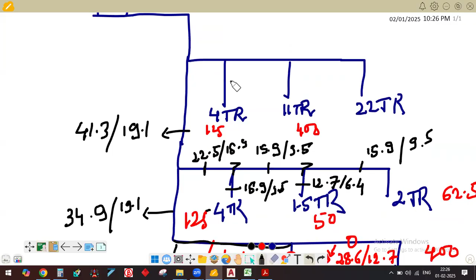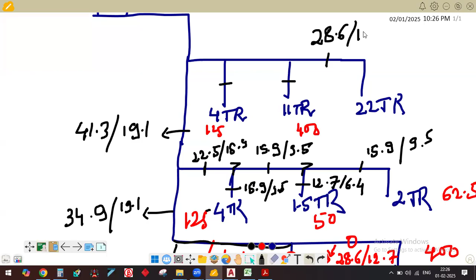Now again, the same exercise we can follow here. Suppose for 125 and 400, we already know the pipe size. Now we don't know the pipe which is connecting to 22 TR. So what do we have to do here? Suppose this situation comes, we are available with the maximum capacity index of 500, which is for 15.9. So either we have to check with the vendor, or we have to go with a maximum size here. Suppose in this example, the maximum size from RefNet to indoor unit is 28.6 and 15.9. I can go with this.